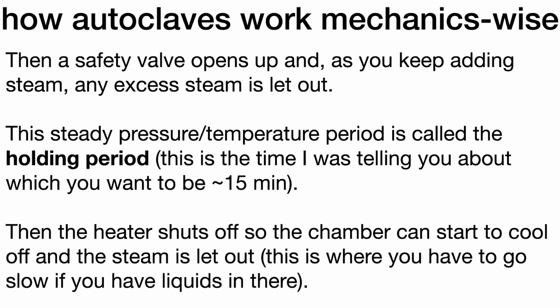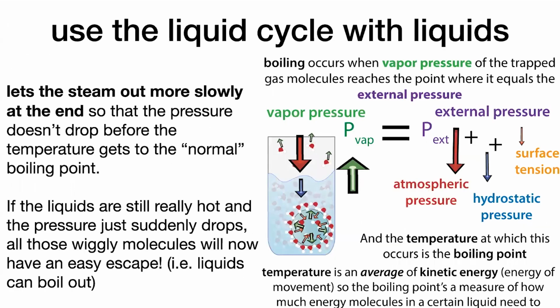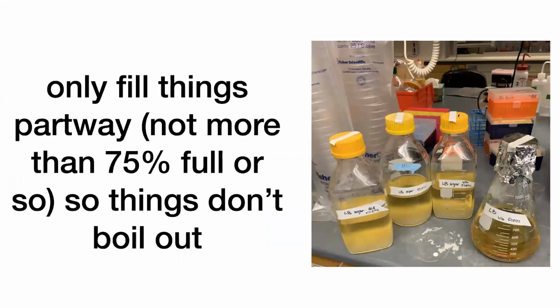Then the heater is going to shut off so the chamber can start to cool off and the steam gets let out. And this is where you have to go slowly if you have liquids in there. Because remember that the boiling point depends on the external pressure. So if that pressure is high, you're going to need a higher temperature in order to boil. But if that pressure drops a lot, now it's going to be easier for things to boil. And if they're still really hot, they're going to be above the new boiling point, and therefore they're going to boil and all your liquids would boil out. And you don't want this to happen.